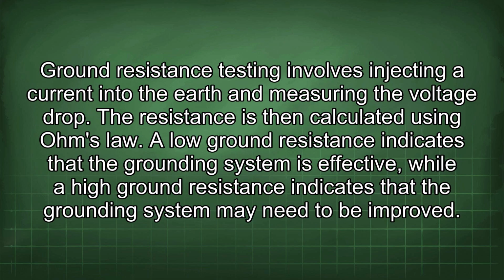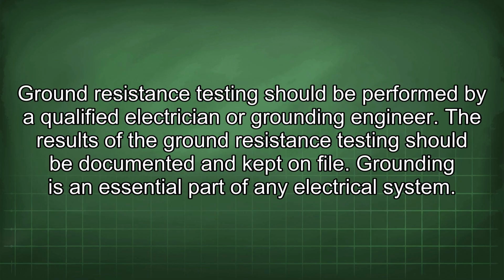Ground resistance testing involves injecting a current into the earth and measuring the voltage drop. The resistance is then calculated using Ohm's law. A low ground resistance indicates that the grounding system is effective, while a high ground resistance indicates that the grounding system may need to be improved. Ground resistance testing should be performed by a qualified electrician or grounding engineer. The results of the ground resistance testing should be documented and kept on file.